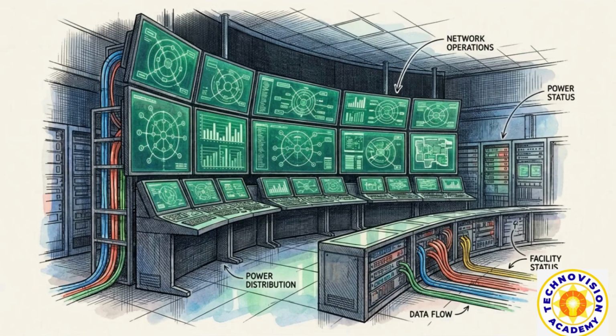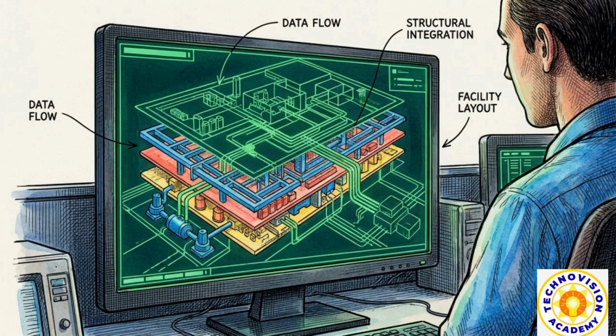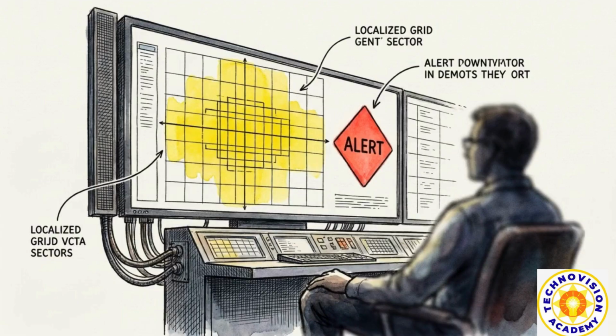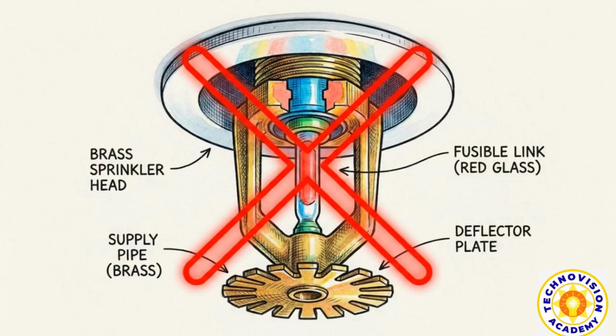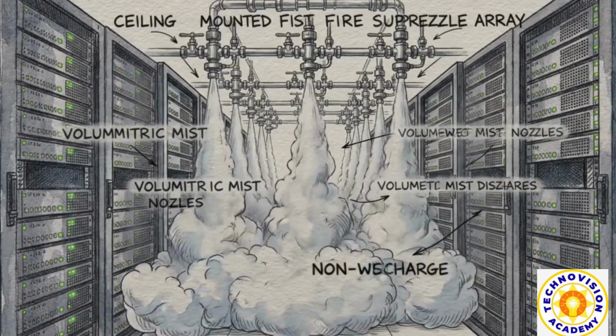Overseeing these mechanical and electrical arteries is the facility's control room. Here, engineers monitor millions of telemetry points streaming from the power and cooling networks. Specialized SCADA and building management system networks tie everything together. This automation allows the building to detect micro-fluctuations, isolate faults, and self-correct anomalies far faster than human reflexes allow. Even fire protection requires precision. Standard sprinklers would destroy the servers, so data centers utilize advanced detection and suppression systems that flood the room with clean chemical agents to extinguish flames without leaving hardware-destroying residue.